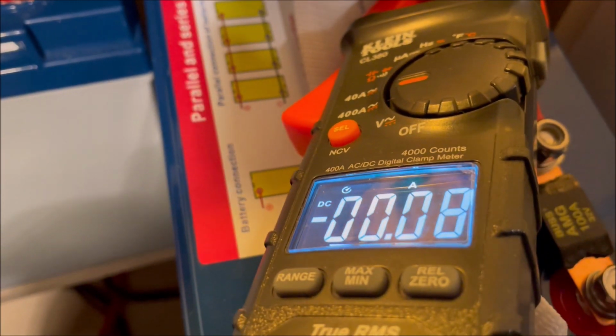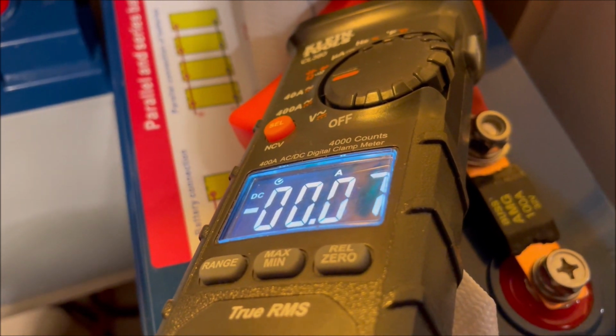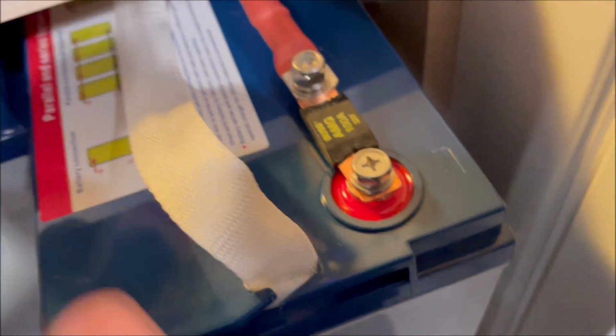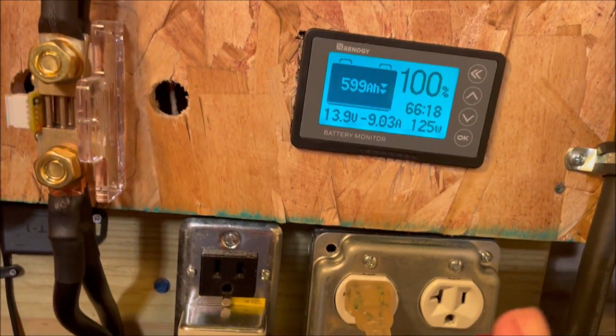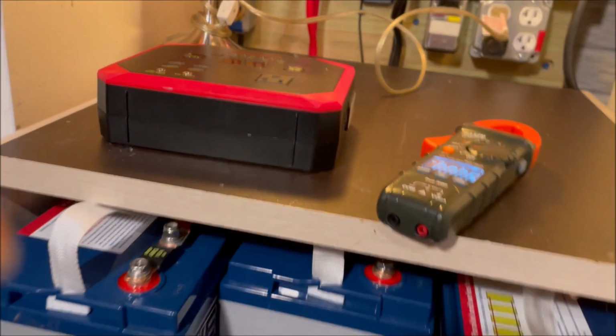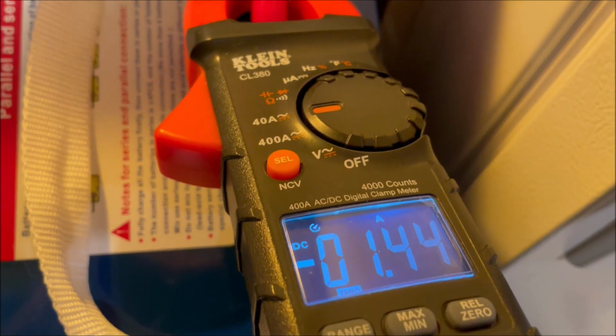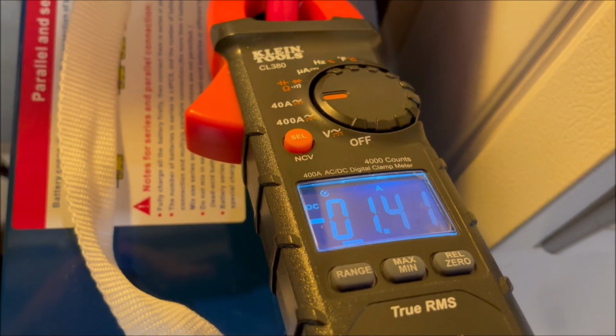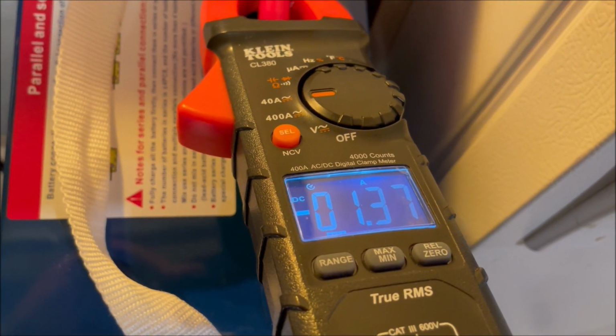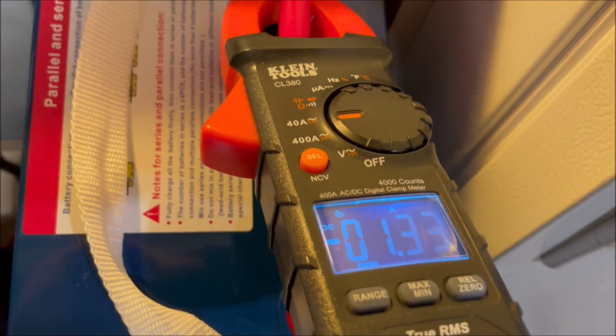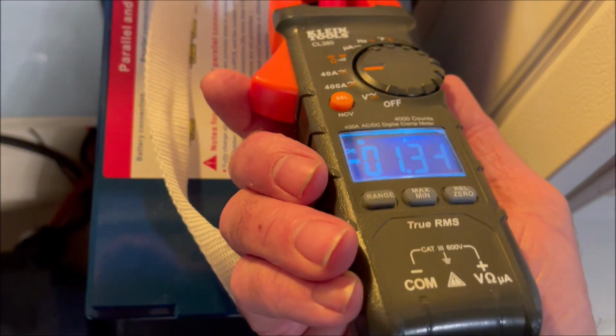Let's go back and check this one. See, this one is still off. It's not really outputting anything. So what we're going to do is let this run here a little while, and then we're going to check it, because once this voltage gets down enough, this battery's BMS will kick in. So we're going to wait and see that. Okay, it's run long enough that this battery's BMS has turned it back on, and now it's outputting and supporting the load.